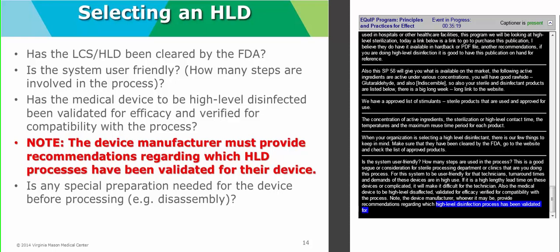Also, has the medical device to be high-level disinfected been validated for efficacy and verified for compatibility with the process? Note that the device manufacturer, whomever that may be, must provide recommendations regarding which high-level disinfection process has been validated for their device. And also, is there any special preparation needed for the device before processing, like disassembly? Are there parts to be taken off? Does it come apart? Those types of questions should be asked.